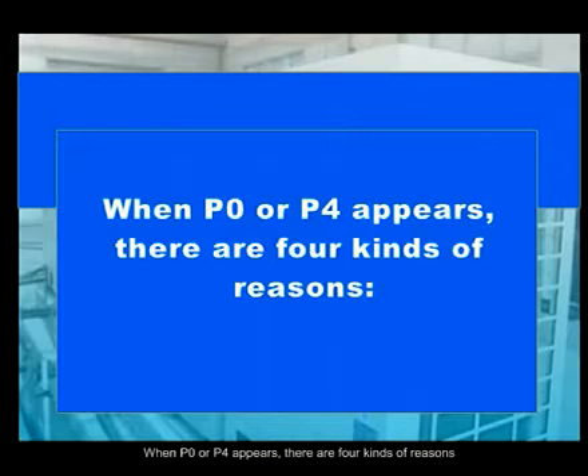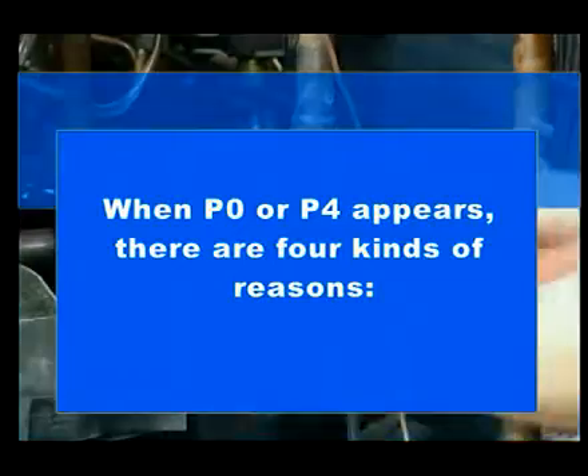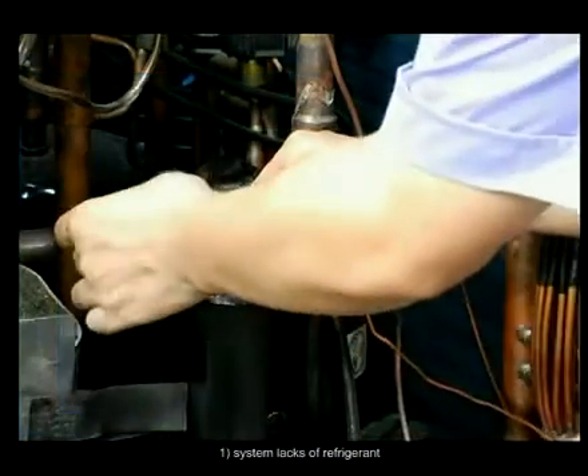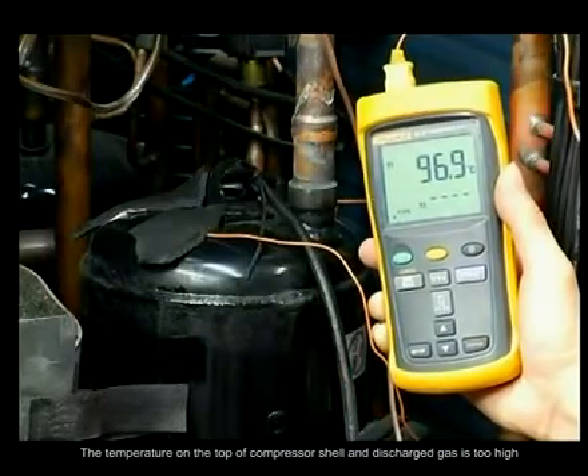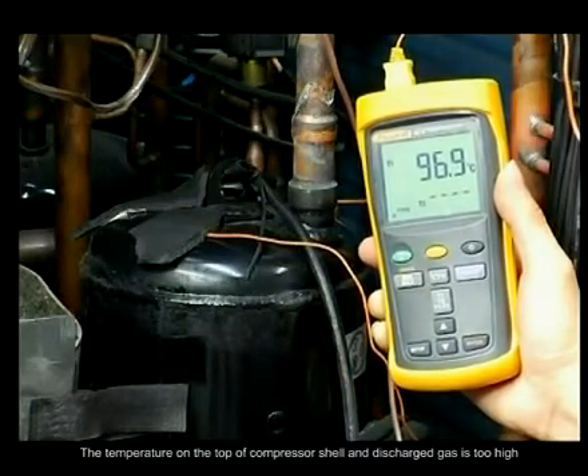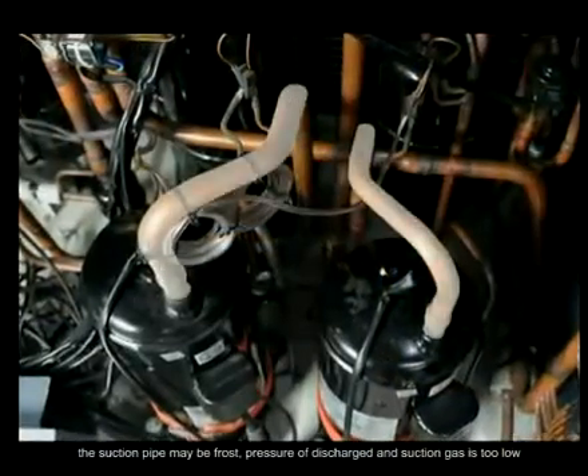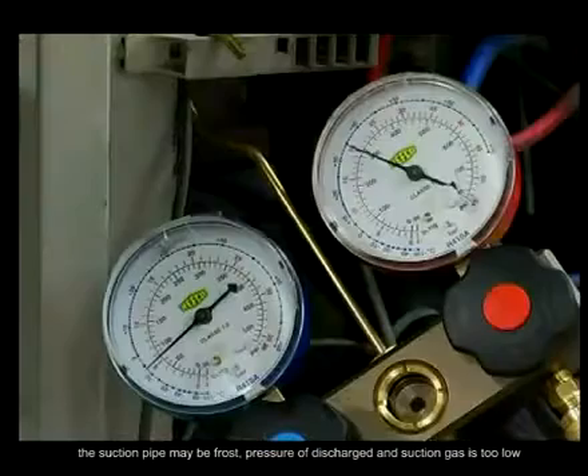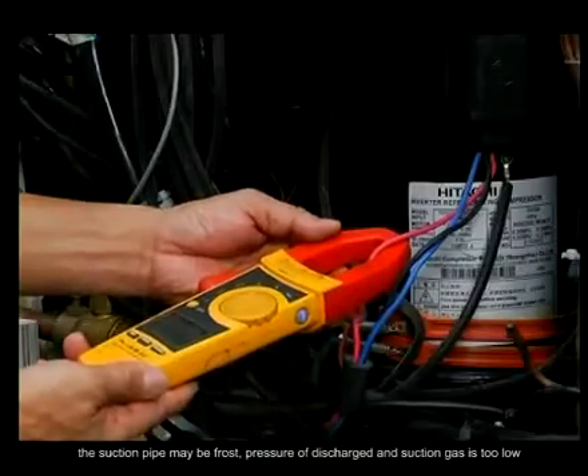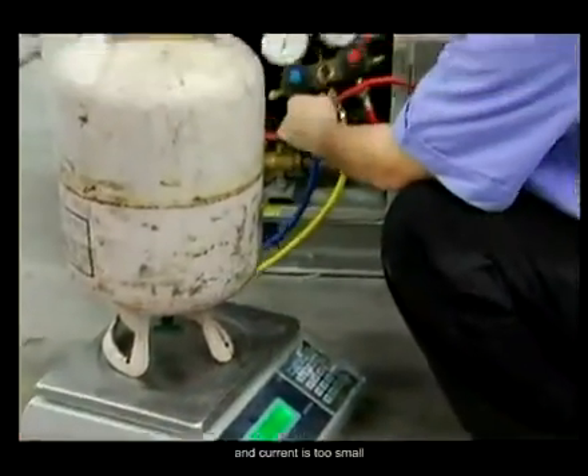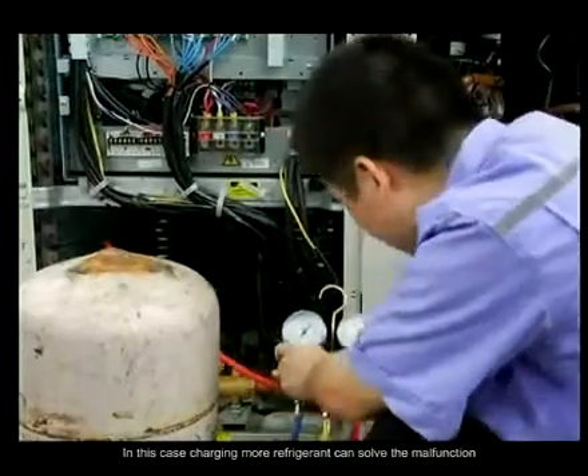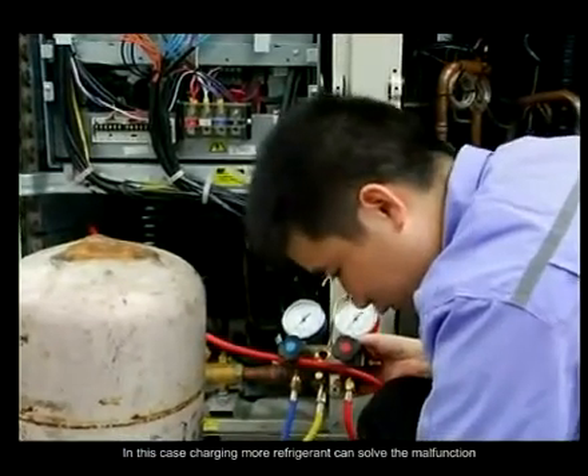When P0 or P4 appears, there are 4 kinds of reasons. One, the system lacks refrigerant. The temperature on the top of the compressor shell and discharged gas is too high. The suction pipe may be frosted. Pressure of discharged and suction gas is too low, and current is too small. In this case, charging more refrigerant can solve the malfunction.